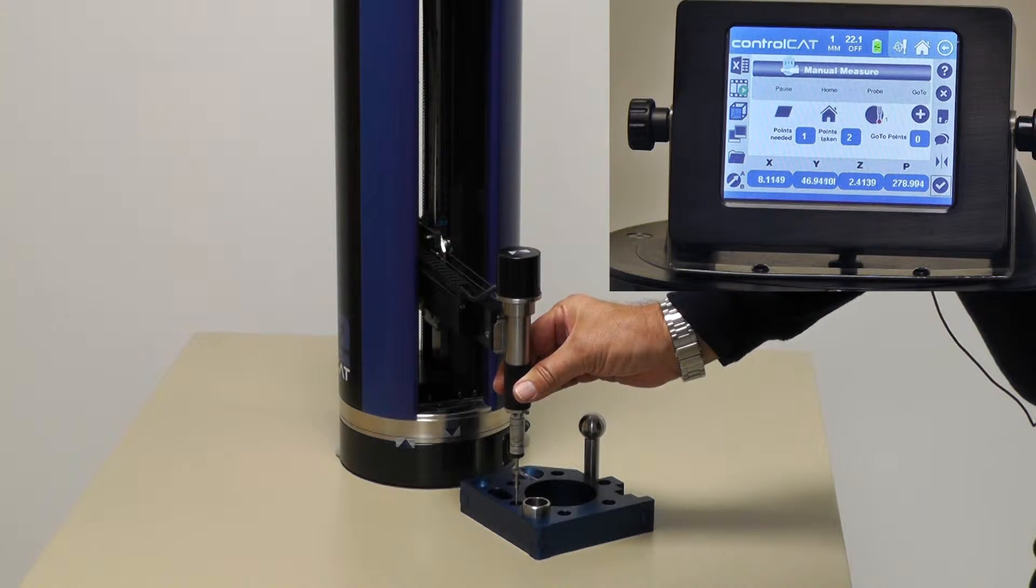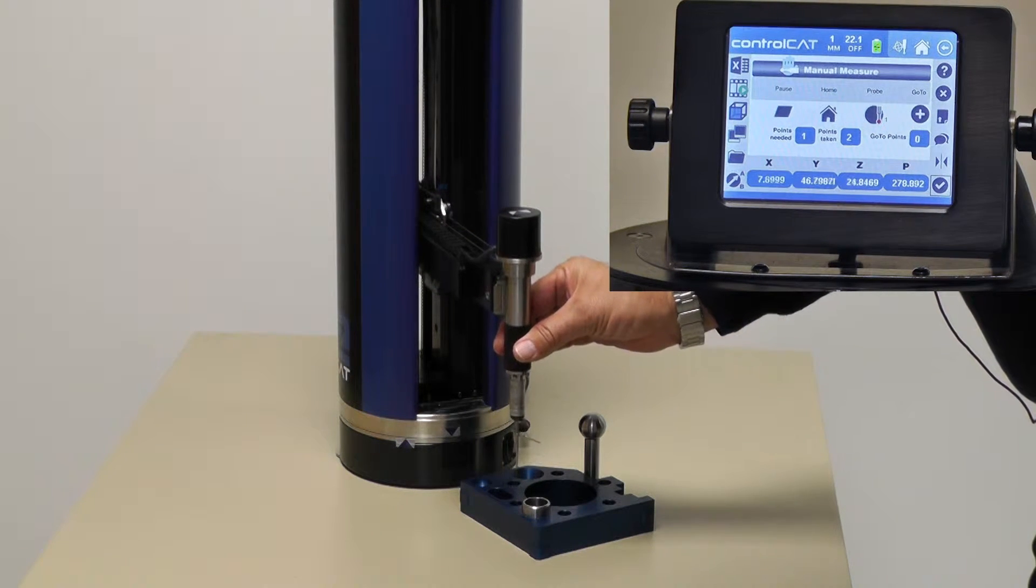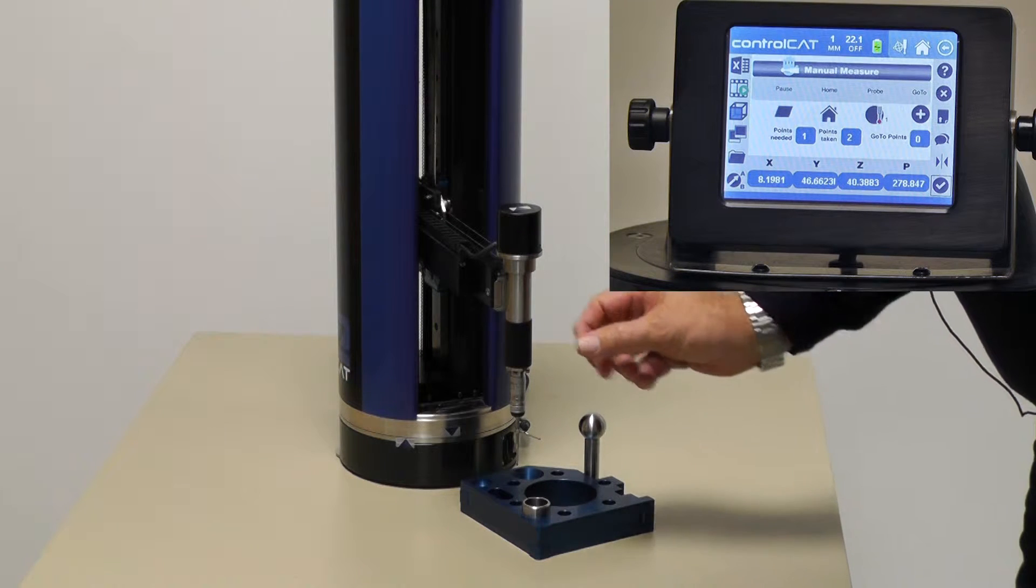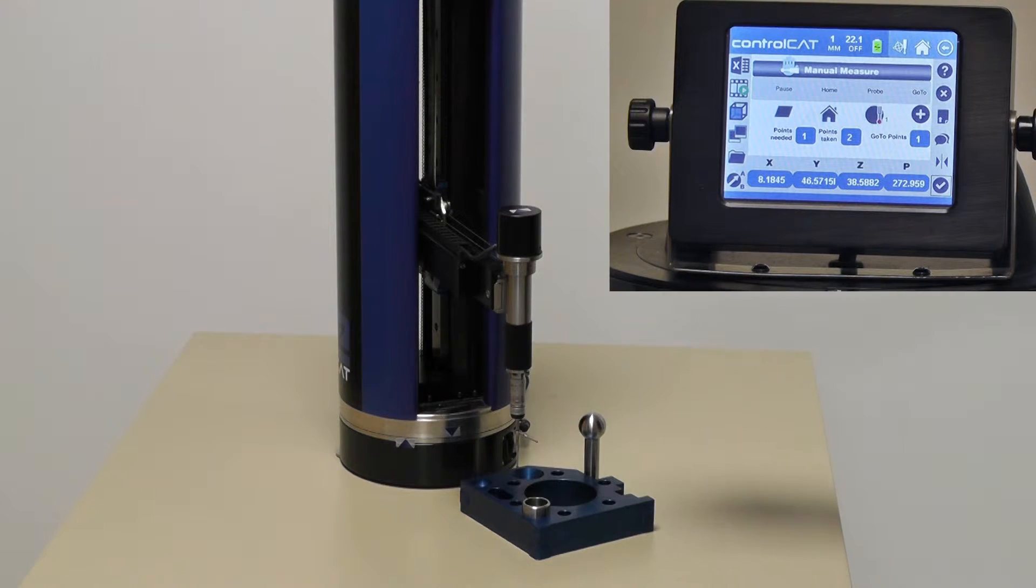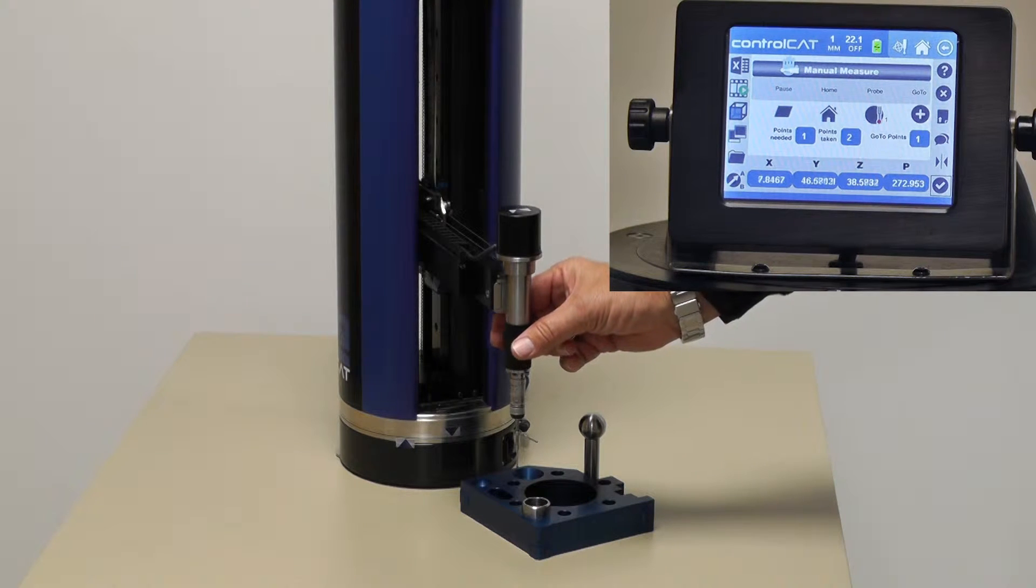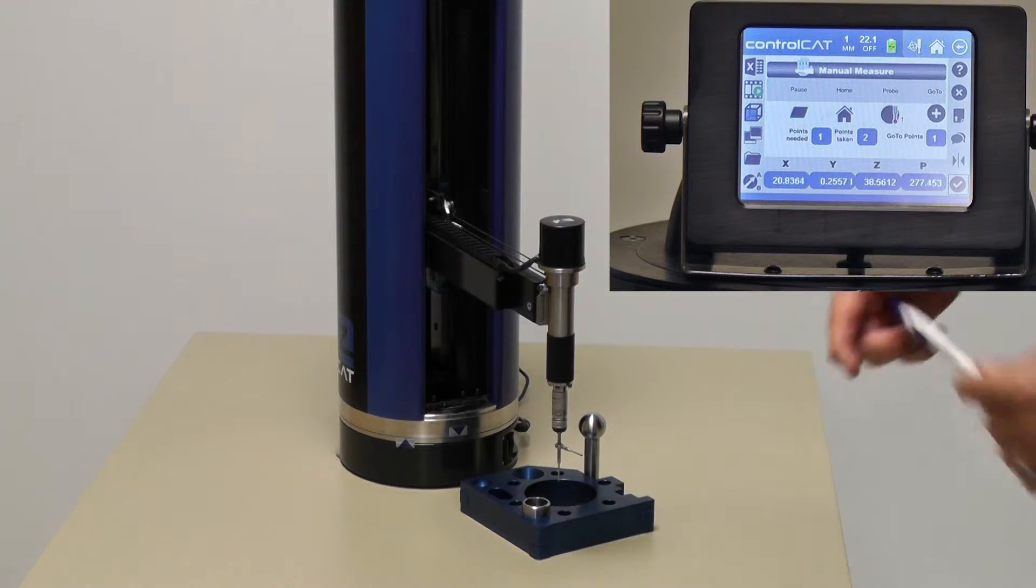Rather than hit this dimension or this raised part, I might raise the gauge up and I can give it a quick twist and that will drive the Zcat probe to that location. I can move it to another location.